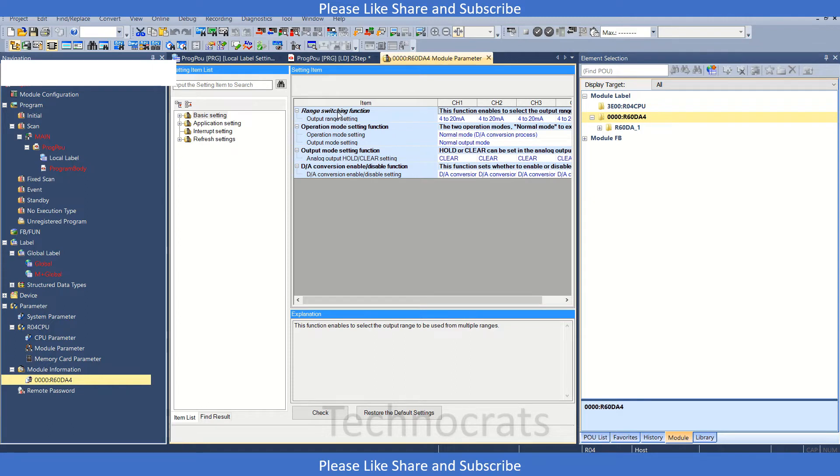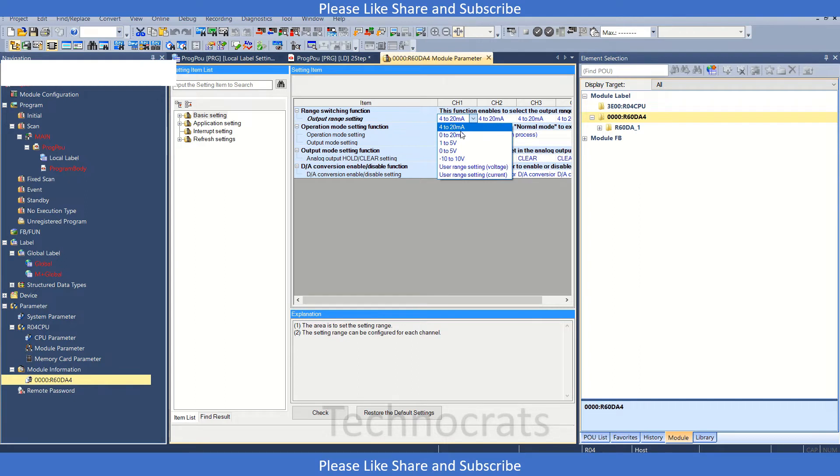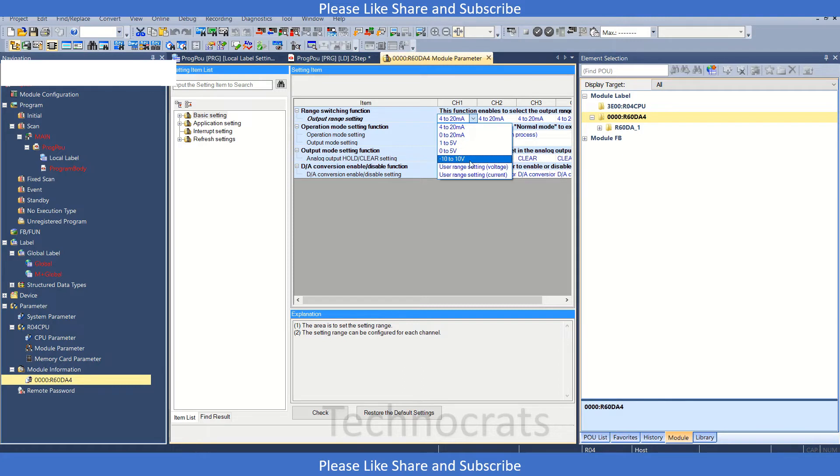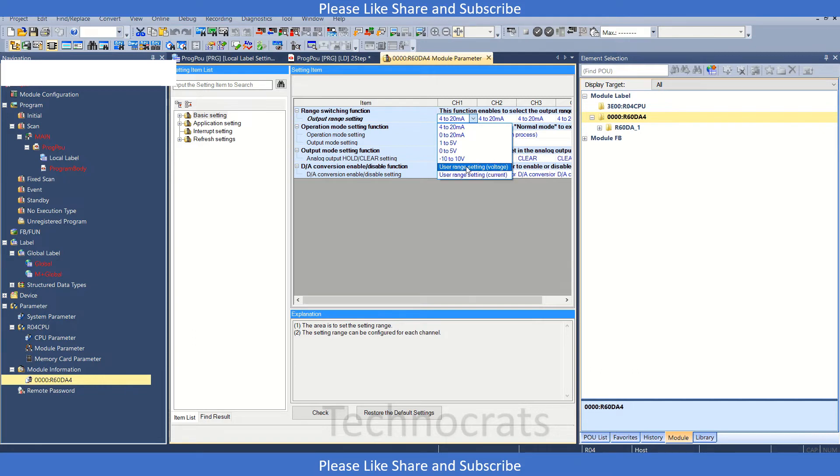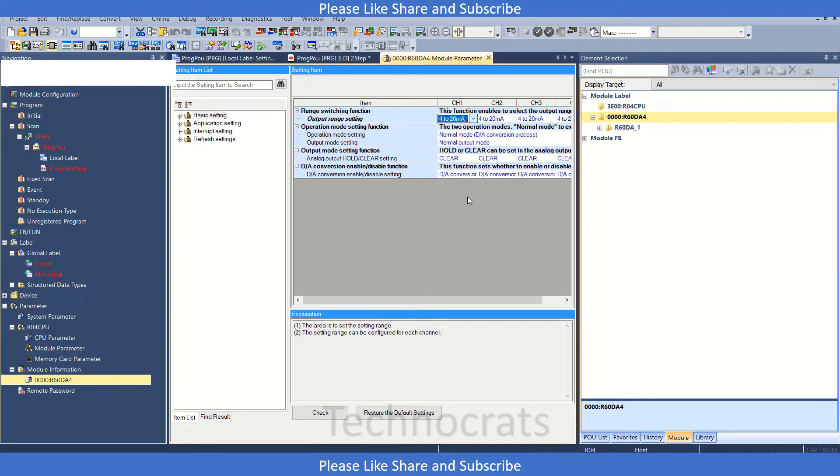Here's the range switching function. We have 4 to 20 milliamps, 0 to 20 milliamps, 1 to 5 volts, 0 to 5 volts, minus 10 to 10 volts, and user-defined ranges. If you want 8 to 20 milliamps or 2 to 5 volts, 2 to 10 volts, or 2 to 8 volts, you can select user range setting and make your own range for the analog output for all four channels.